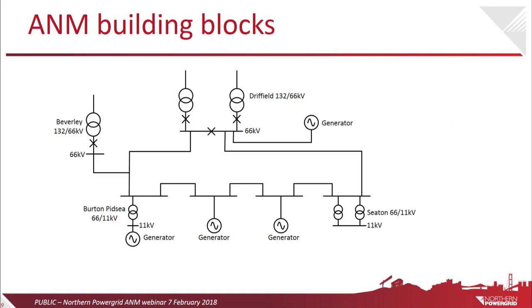So, what constraints do we have, and what does the scheme look like? We have reverse power flow constraints on the grid transformers supplying the 66 kV network. These are the ones that I was talking about would need replacement for a traditional scheme. In addition to that, we have circuit constraints on the Driffield ring, where ratings of overhead lines limit the amount of power that can safely flow around that overhead line network. There's about 72 kilometres of overhead line network on that Driffield ring that's on screen at the moment, coloured in red.